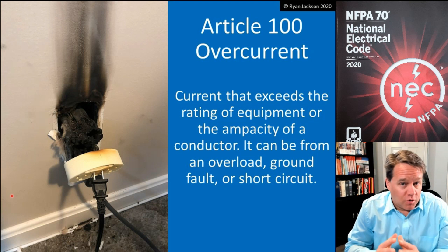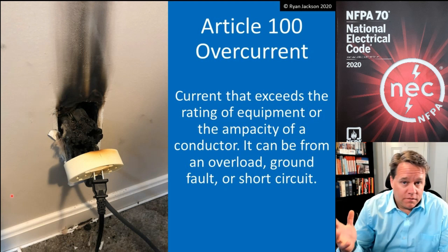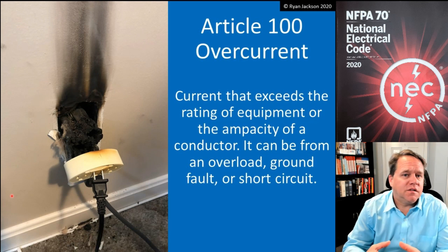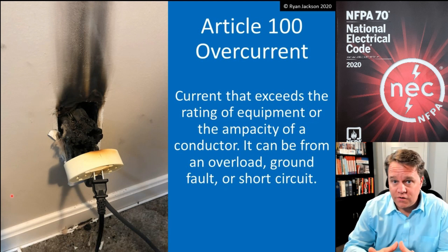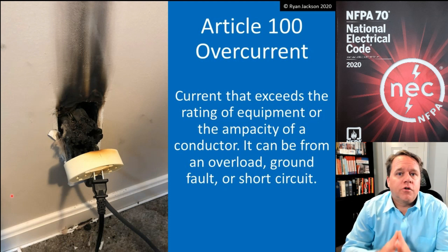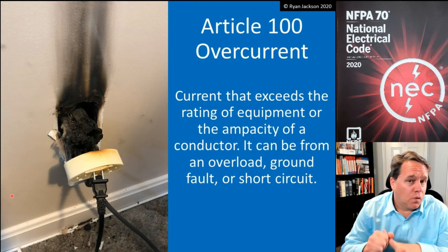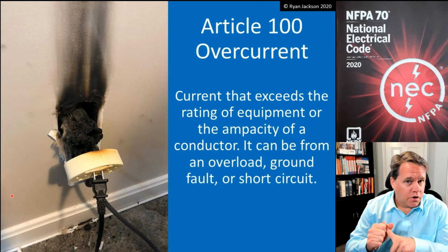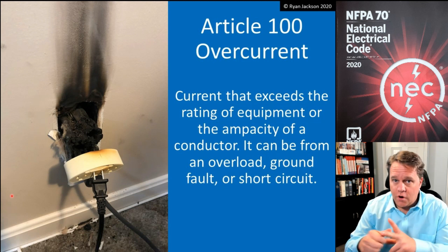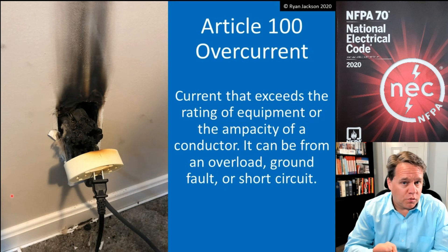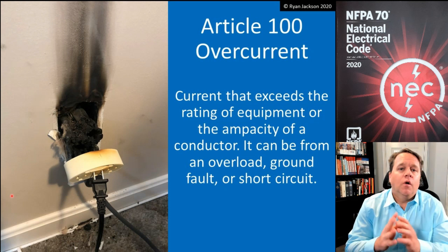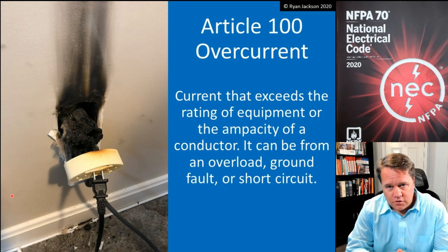When it comes to the definitions in Article 100, some of them are very simple and some are not. Overcurrent is a definition that is somewhat simple but fully understanding it is a bit more complex. Overcurrent is defined as current that exceeds the rating of equipment or current that exceeds the ampacity of a conductor. Both conductors and equipment can be subjected to overcurrent, and we have to protect both.